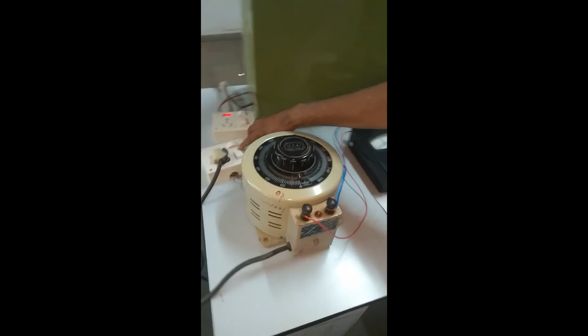So before going for calculation, we can turn it off. The voltage needs to be 0, and then we can switch off. Now we will go for the calculation. Now we have the short circuit voltage, short circuit current, and short circuit power. So we can determine the equivalent resistance using this formula, WSC upon ISC square. WSC is with us, the short circuit current is with us, so substitute the values, do the math, and you will get the value of equivalent resistance referred to primary.